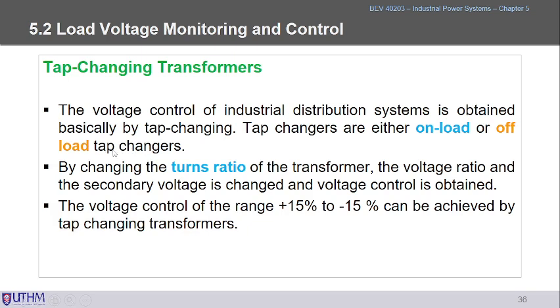Of course, it is much cheaper than on load tap. It depends on the turn ratio also. The normal voltage control is that you can adjust within the range plus 15% to minus 15%. This is within the permissible voltage level of plus minus 10%, that means you get an extra 5% as compared to the standards.